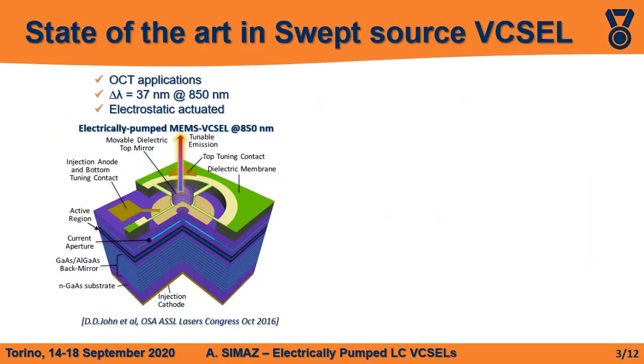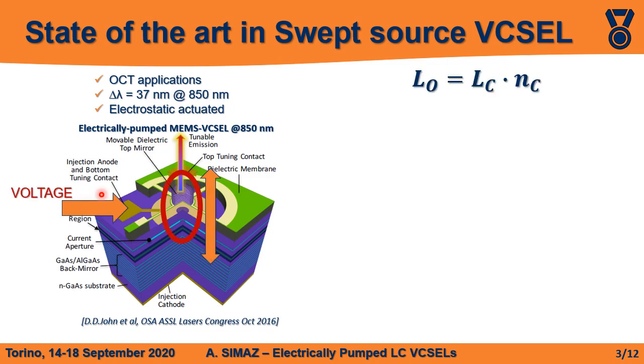Today, the state of the art in swept source VCSELs is represented by MEMS fabrication. Here it is shown an example from John et al., designed to be used in OCT applications. The tuning range achieved by this device is 37 nm at the central wavelength of 850 nm, and it is an electrostatically actuated device, which means that there is a common anode where we inject the current inside the active material to reach the inversion population condition, thus lasing. We apply on the same anode the voltage through a suspended top movable mirror. By applying different voltages, the cavity length can be varied, and accordingly to this formula, we can change the optical length and therefore the emission wavelength.